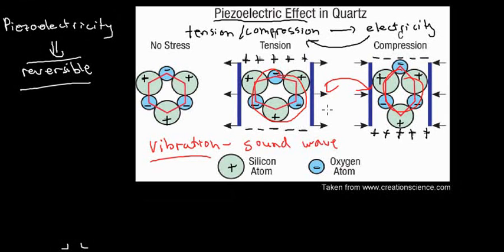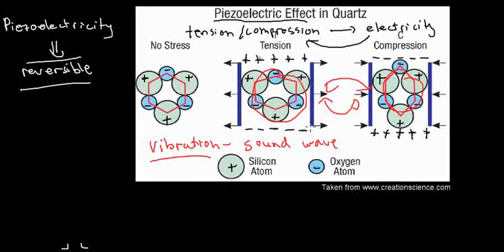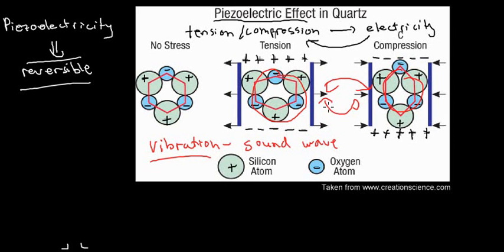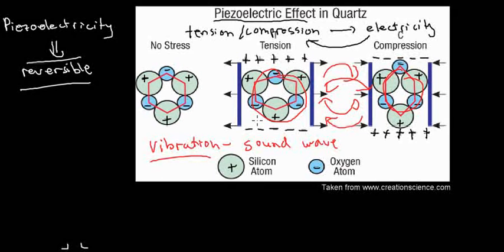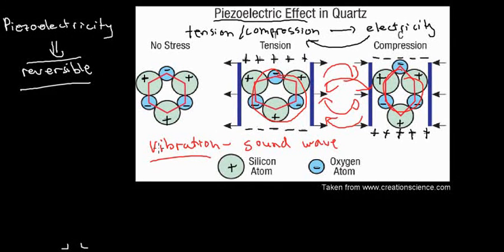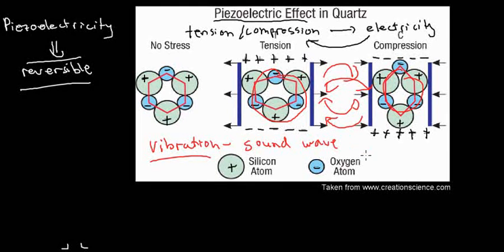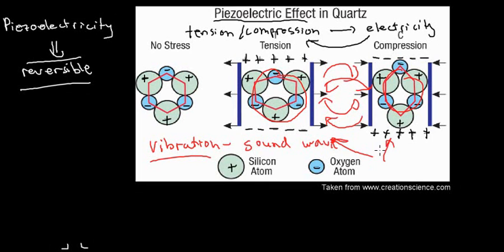So how is it used in ultrasound? Just think of me doing this process of back and forth, switching around the electric currents around this crystal super rapidly. So it's going to go through these transitions a great amount of times in a second and vibrate so quickly that it would emit an ultrasound. Obviously, the quicker I do these transitions from this state to this state, the higher the frequency. So if I do it really quickly, I would get a very high frequency ultrasound.